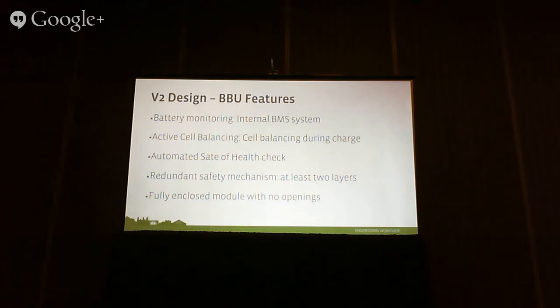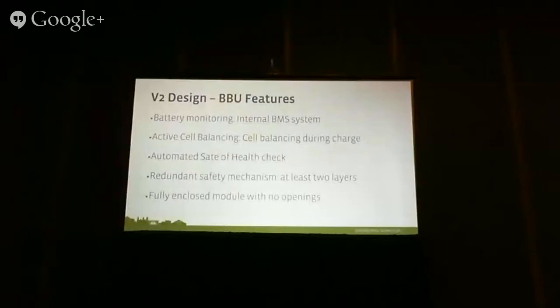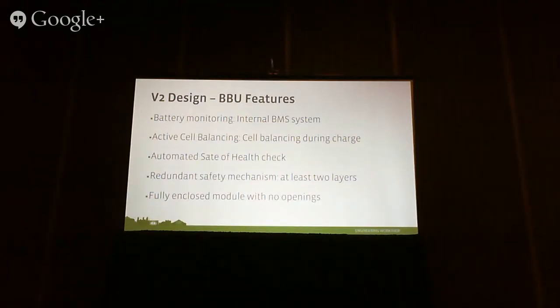Some of the main features this unit has include battery monitoring. We carry everything we had from that blue battery cabinet inside the module, with an internal BMS for every module. That BMS can monitor a lot of variables, everything you can think of in a lithium-ion cell: voltage, current, temperature, coulomb counting, rate monitoring. It pretty much follows the smart battery monitoring standard that's out there, and more. We communicate through the power supply to the BBU, and we can read variables through the power supply.